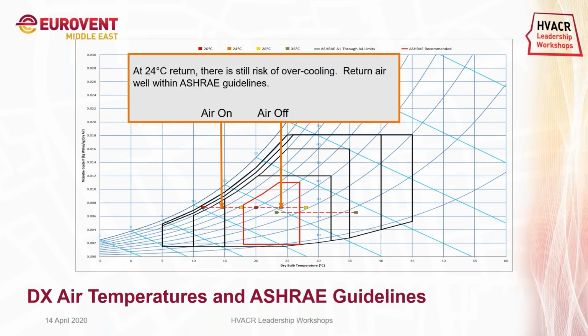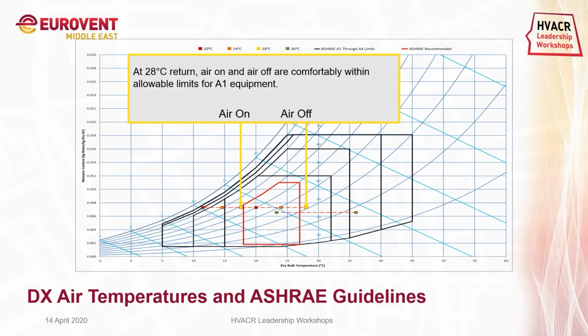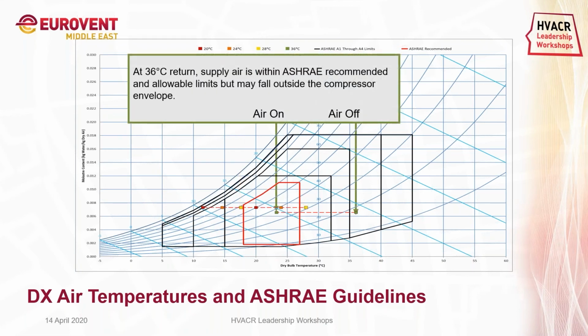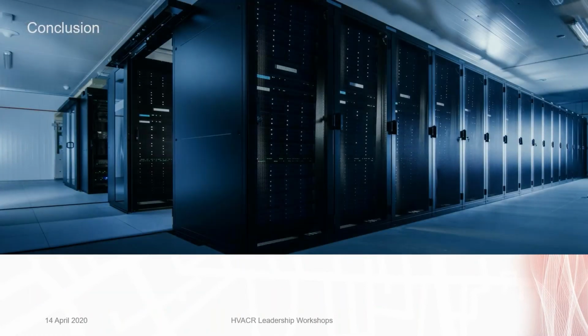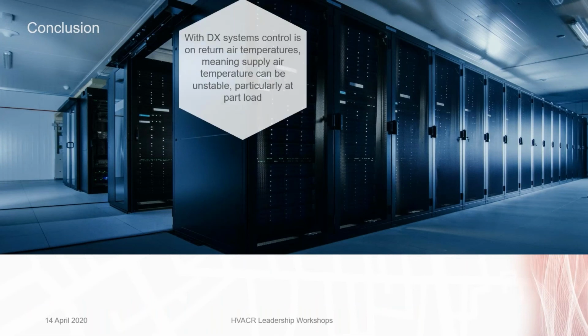At 24 degrees Celsius, it's still below the recommended range, still a risk of overcooling, but the return air is well within the ASHRAE guidelines. At 28 degrees Celsius, air-on and air-off are comfortably within the allowable limits of A1 and very close to the recommended range of ASHRAE. At 36 degrees Celsius, supply air is well within the ASHRAE recommended range, but this may fall outside the compressor operation envelope. So that's the conclusion with the DX system.